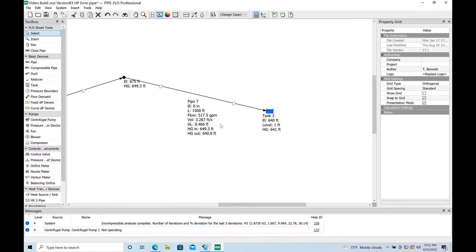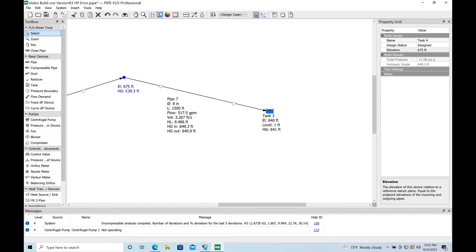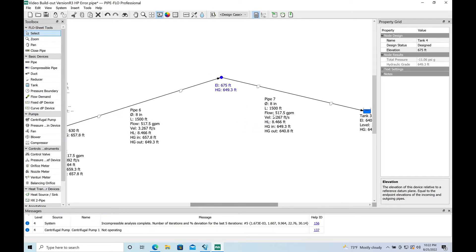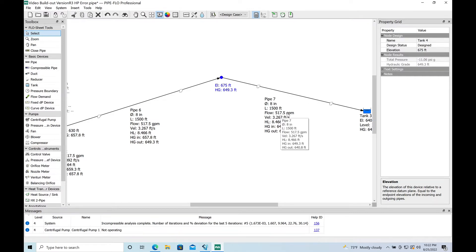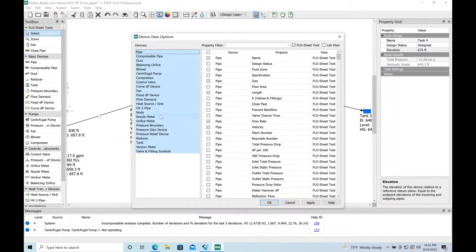Now we've got two pipes in there and basically now we have a force main that is twice as long. A couple of things to watch out for here. I'm already wondering why I'm pumping more flow through a force main that is twice as long. That should immediately start to ring bells with you. If it doesn't, then you've got to do this in your pressure systems.